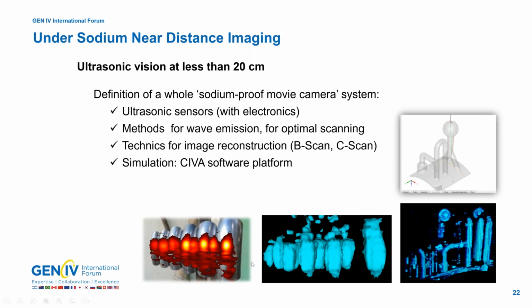What you see at the bottom of the slide are some elbows with the echoes, which are in orange. So you see a real picture, optical picture, and then the acoustic echoes on the same slide. And what you see, there are only 6 elbows and more echoes. So you see that using ultrasonic systems, sometimes you can have some trouble when trying to image such a system. And on the right, what you see is a specific mock-up we developed with a number of specific designs: pipe, bowl, Y shape, U shape, T shape, and that was used for underwater first and then under sodium tests.